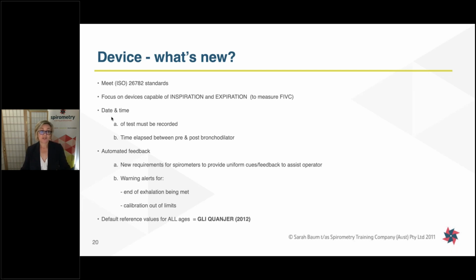Devices now need to record the date and time, not just of each test, but also of the time that's elapsed between pre and post bronchodilator. They're also now required to provide automated feedback in a standardized way. So there are new requirements to provide this uniform feedback, and that's to assist operators. It's also now required to give you a warning alert. So at end of exhalation, we need to hear an audible and sometimes visual alert so that we can identify that the subject has met end of exhalation. But it should also be alerting us now when the calibration is out of limit. So there are some really great updates to requirements for devices.